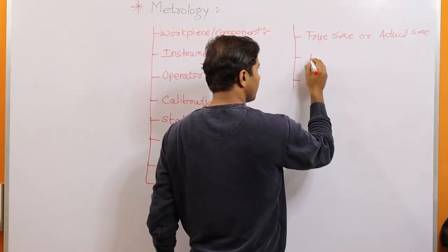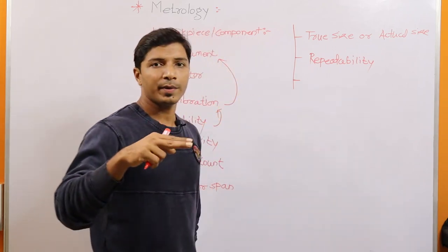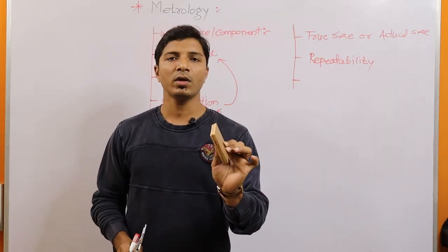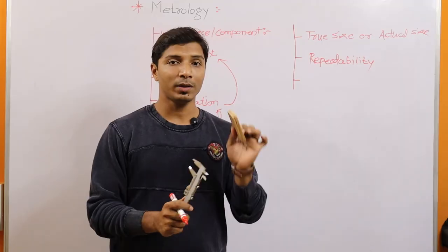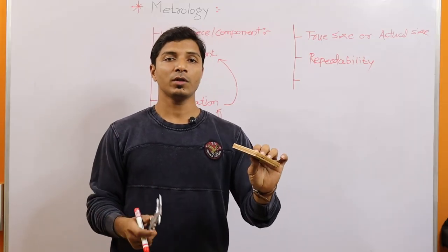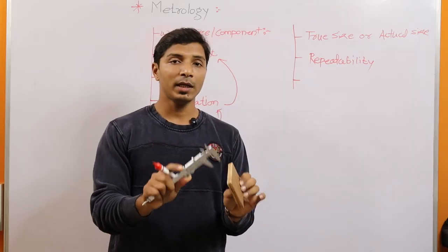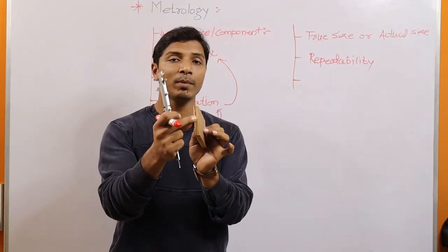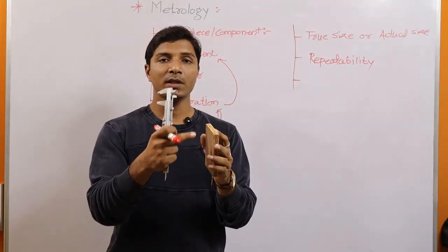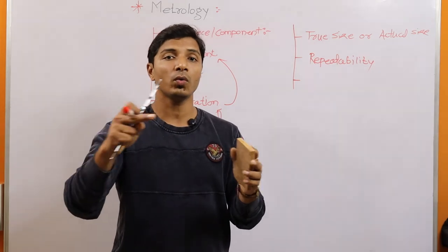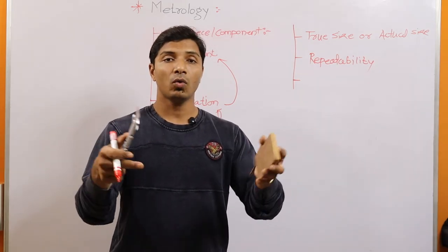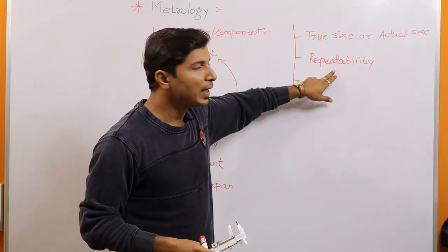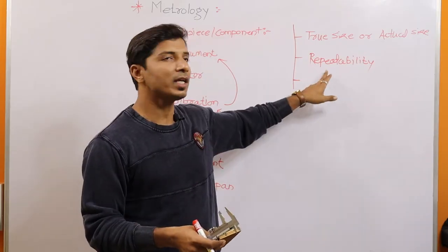The next parameter is repeatability. To understand it, assign a thousand components to a single operator and have them measure all components with a single instrument, then observe whether the results are close together. For example, if this side is 10 mm and measurements come out as 10.001, 10.002, 10.003 — all close together — then the instrument has repeatability, meaning the ability to repeat results with closeness.